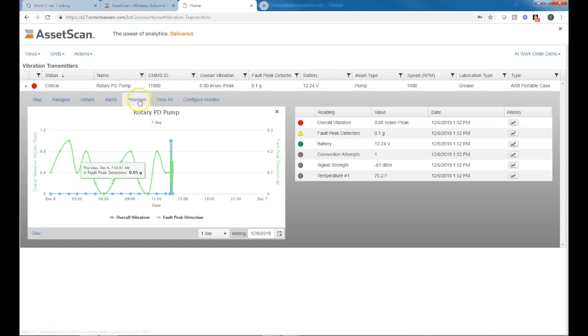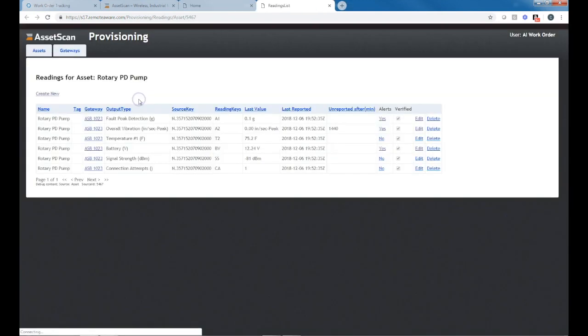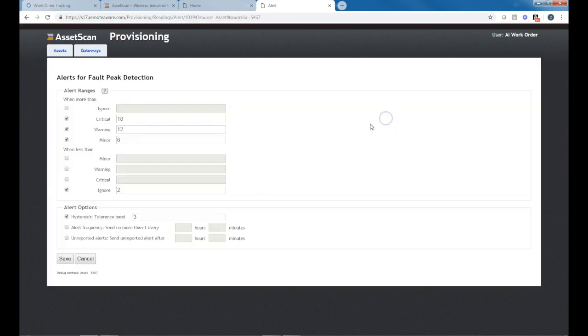Taking a look at how we set up our alerts in AssetScan, we can go to our fault peak detection. This is based on high frequency or ultrasonic data. Our standard alerts are 6, 12 and 18 Gs, which we also cover in another video.